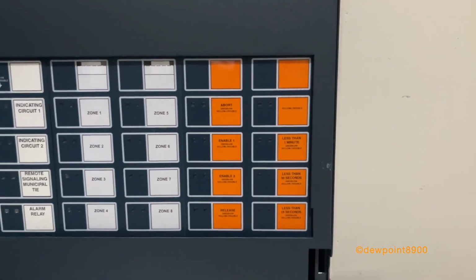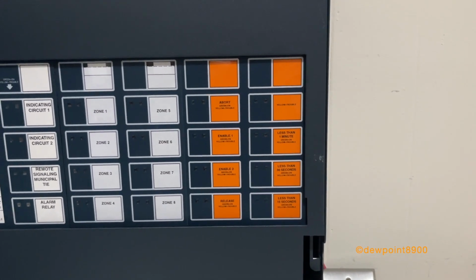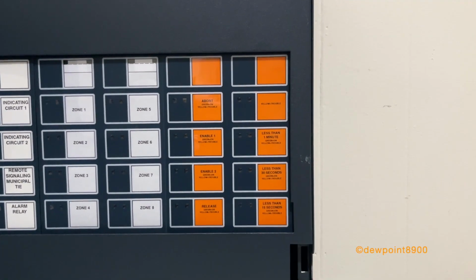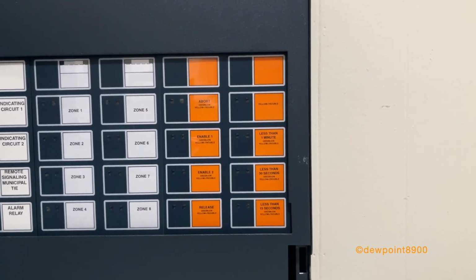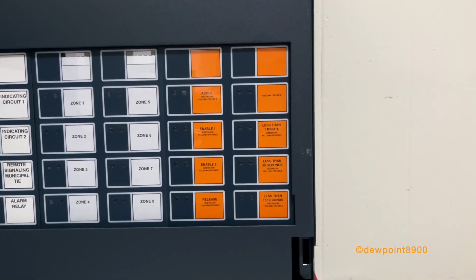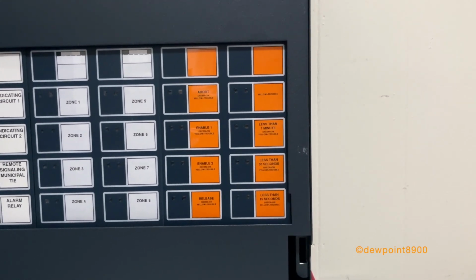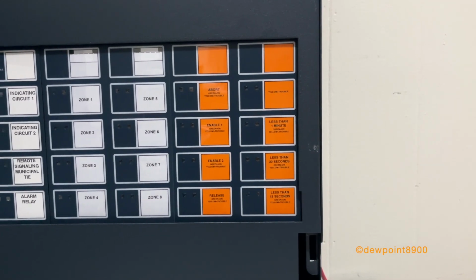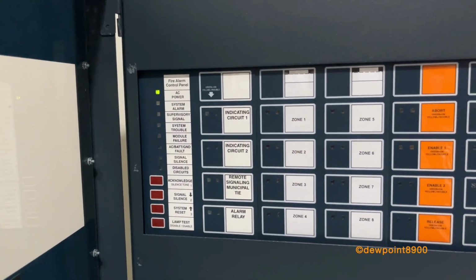So this System 500 has a suppression release system programmed to it. And to do this, it has a TC2 timer card on it. The TC2 timer card is in the same group as the TC4, providing suppression release and dual-stage coded outputs. While the TC4 has more circuits, the TC2 is more detail-oriented, with programmable time delays, an abort switch, and zones for controlling the outputs. All programming is accomplished on the CPU, as per usual.